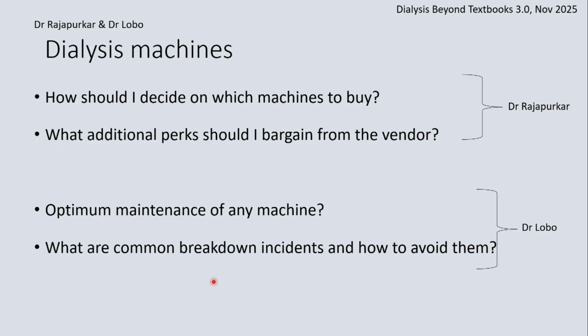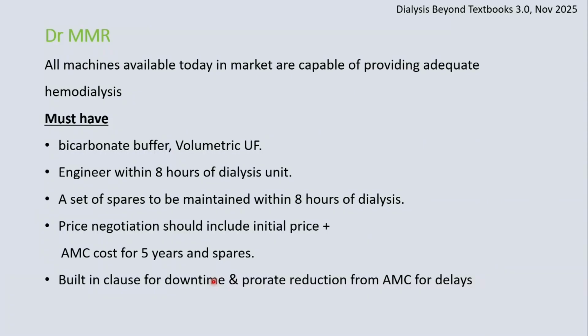Any machine that is manufactured and available in the market today can provide adequate dialysis, if you know your machine and are able to deliver it. So you can buy any machine that gives you the best buy at that point of time. Of course, it must have bicarbonate buffer, preferably solid bicarbonate. All machines nowadays have volumetric UF, but this was written several years ago when machines did not really have true volumetric UF. The engineer should be within 8 hours of the dialysis unit. A set of spares should be maintained within 8 hours of the dialysis unit.